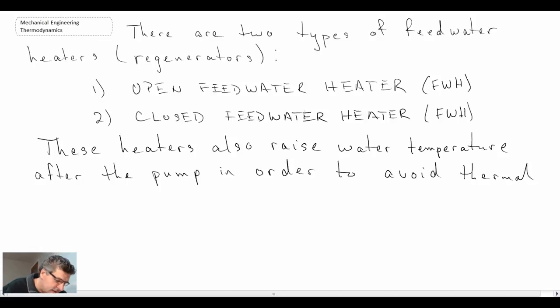So another advantage that we get out of these systems is that they minimize the amount of thermal shock to the boiler metal when we introduce a cold liquid coming out of the pump. We heat up that liquid out of the pump, the feedwater, and consequently minimize any kind of thermal shock to the metal.